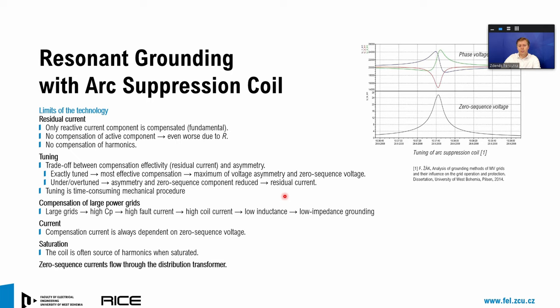So what are the limits which I see with the arc suppression coil operation? Definitely one of the big problems is residual current, because the arc suppression coil is able to compensate only a reactive current component of the fault current, and it is able to compensate only a fundamental component of this fault capacitive current. The arc suppression coil is unable to compensate the active fault current component, and it is unable to compensate the higher harmonics in the fault current.